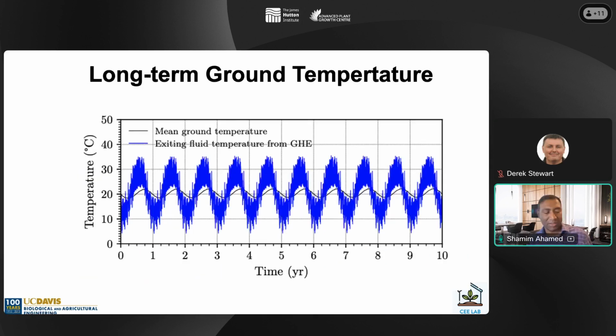The next slide gives an overview of how the hybrid system helps control ground temperature. Even over 10 years of simulation, you can see the fluctuation of the exit fluid temperature for the ground heat exchanger, with the black line indicating ground temperature. It's almost balanced out when you optimally design the ground heat exchangers and the ground source heat pump. This helps minimize the issues that conventional ground source heat pumps face, especially in regions where heating or cooling cost is very high and imbalanced, since there's an easy chance for ground temperature imbalance that can make the geothermal technology stop working.